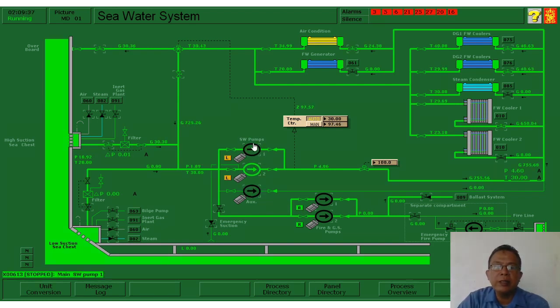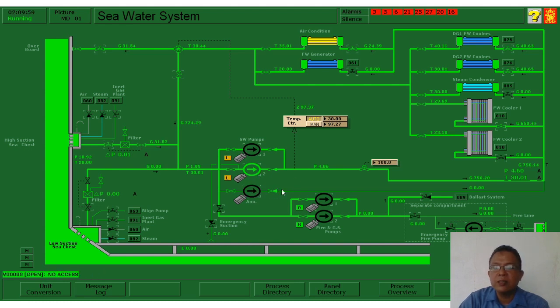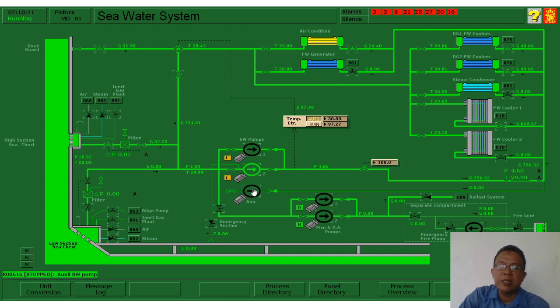Here we have the seawater main cooling pump number one and seawater main cooling pump number two — the main seawater cooling pumps, which are bigger than the auxiliary seawater cooling pump. The auxiliary pump is only used when the ship is at port, as it is only necessary to cool down some restricted coolers because the main engine is not in use. So we need only the smaller seawater cooling pump.